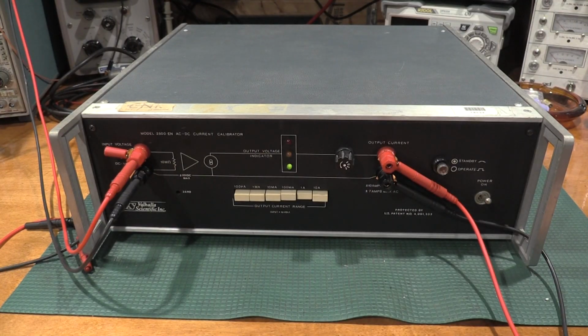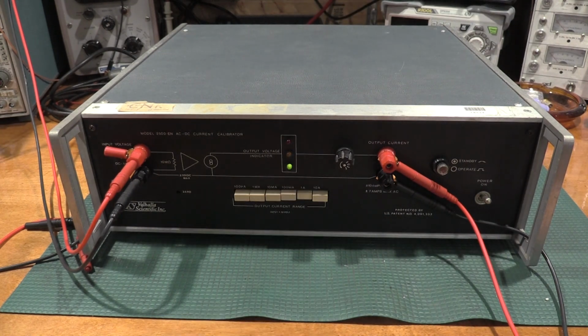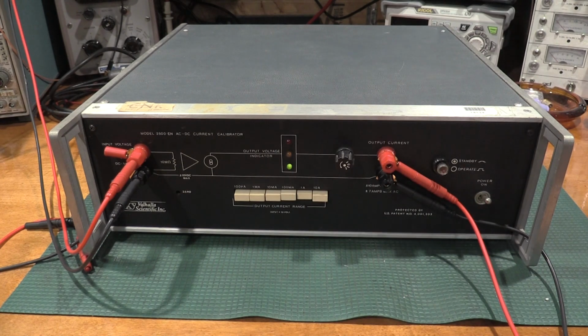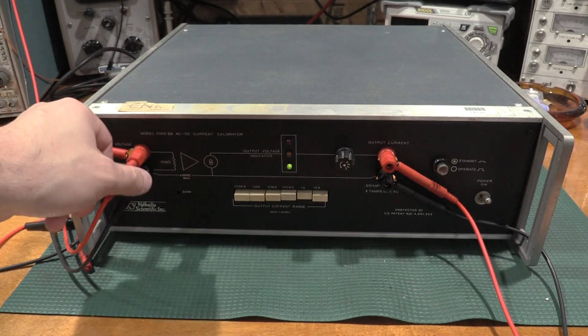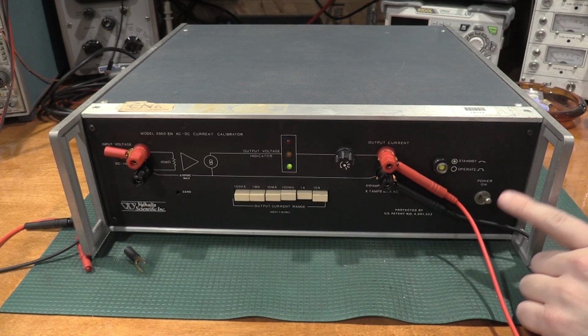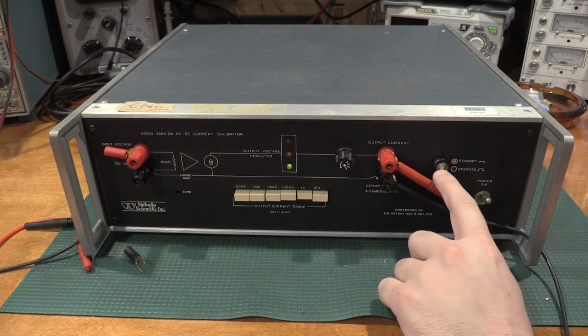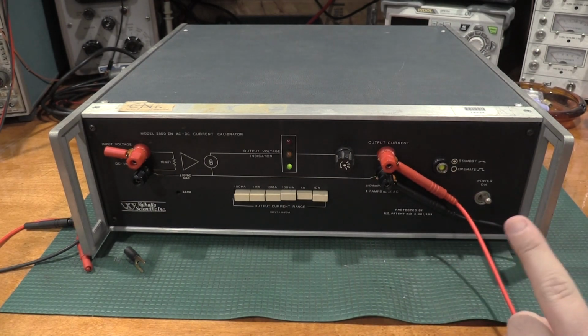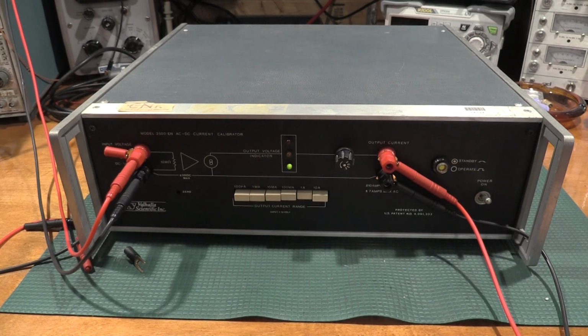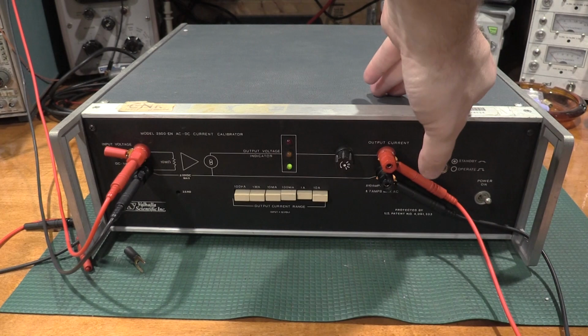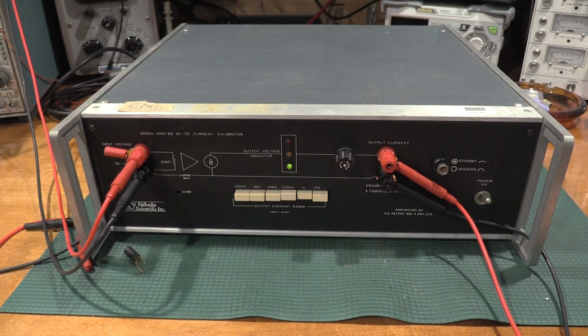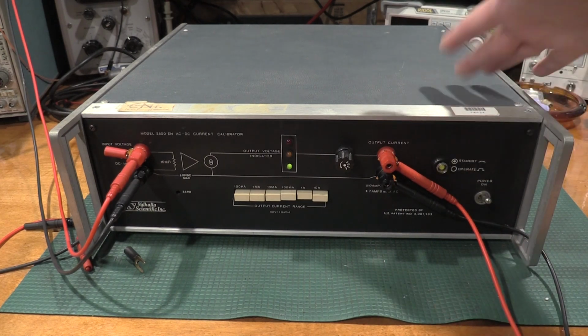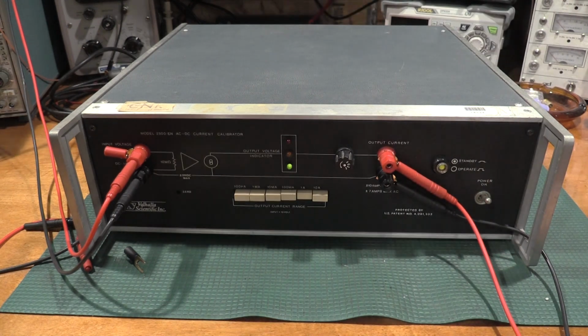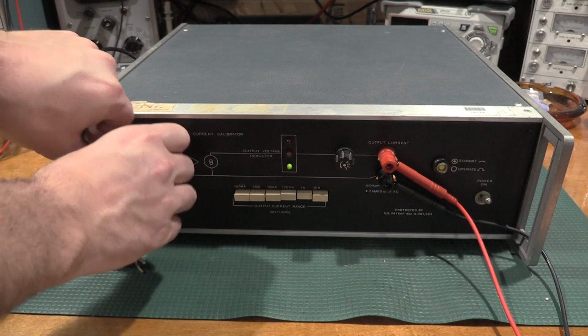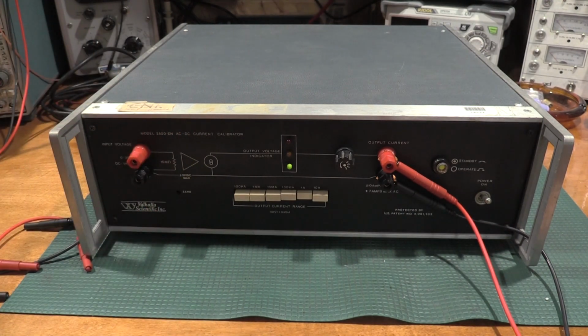As always, sometimes in the lab, we take one step forward and half a step back. In this case, we did. Not a problem, though. The shunt resistors are probably the easiest side of things to pick up. I hate that setting. I really wish it was green when it was operating, and it was not green when it was in standby. That's very confusing. Make sure something didn't happen real quick. Give it input voltage. Set it to operate. Yeah, we're fine. So, we will do this in the correct order now. Stand by. Turn off the input voltage, control voltage, and shut down the unit.